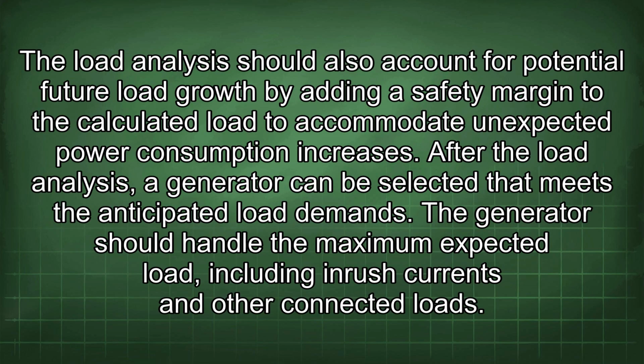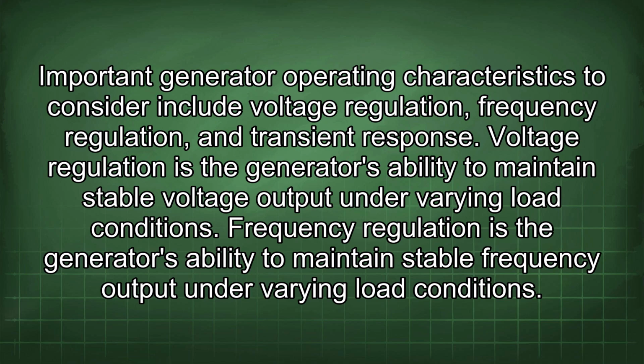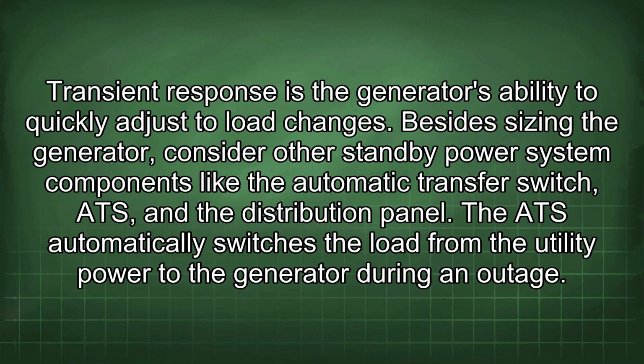The load analysis should also account for potential future load growth by adding a safety margin to the calculated load to accommodate unexpected power consumption increases. After the load analysis, a generator can be selected that meets the anticipated load demands. The generator should handle the maximum expected load, including inrush currents and other connected loads. Important generator operating characteristics to consider include voltage regulation, frequency regulation, and transient response. Voltage regulation is the generator's ability to maintain stable voltage output under varying load conditions. Frequency regulation is the generator's ability to maintain stable frequency output under varying load conditions. Transient response is the generator's ability to quickly adjust to load changes.